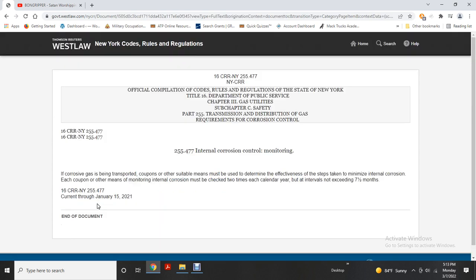Internal corrosion control monitoring: where corrosive gas may be transported, coupons or other suitable means must be used to determine the effectiveness of steps taken to control internal corrosion. Each coupon must be checked at least twice each calendar year at intervals not exceeding seven and a half months.